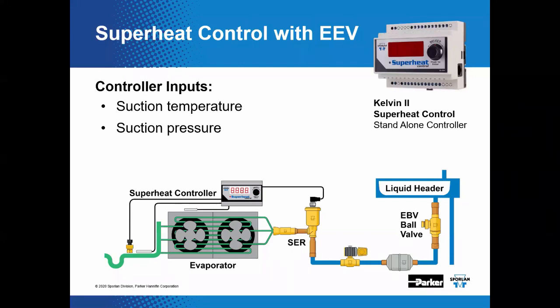EEV controllers can be categorized as standalone or integrated. Sporlan standalone controller, as you can see here, the superheat control is built on the Kelvin 2 platform. Its sole purpose is to control superheat. It uses a temperature sensor. Where's that temperature sensor? Can you see it on here? There it is right there. It uses a temperature sensor and a pressure transducer to calculate superheat and then positions the EEV accordingly.